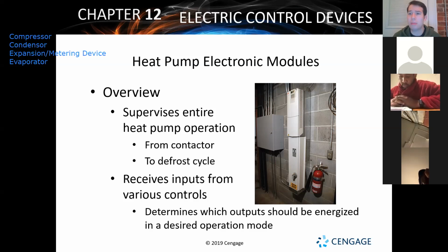It'll also be able to anticipate the temperature it's got going on outside. If it's got an outdoor temperature sensor with these controls, this will let it know, yes, you can turn on the heat pump mode, or no, the heat pump's not going to work, and we need to turn on either the gas furnace or, more typically, the electric heat. You've probably had it before where the heat kicked on, maybe the first time of the season, or on a really, really cold night when the temperature drops to the 20s, and you wake up and smell that kind of burning smell and wonder what that is. That's the electric heat kicking on because it's gotten too cold outside. The heat pump can't operate, and the system's told it, hey, don't even try. Just turn on the electric heat and keep that going for now. So that's how these things are going to be operating.